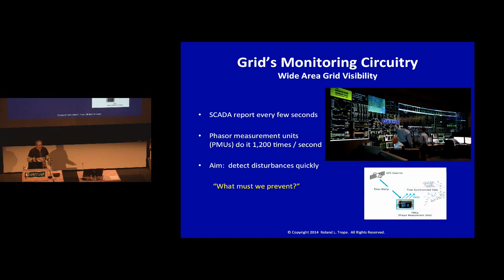Disturbances can arise from an over or under amount of voltage, a loss of a transmission line as in a storm, or transformers failing as they do. Many of these transformers are 40 or 50 years old and they're beginning to fail, but they can also fail if they're attacked, or if a disturbance gets into them and it isn't stopped in time.